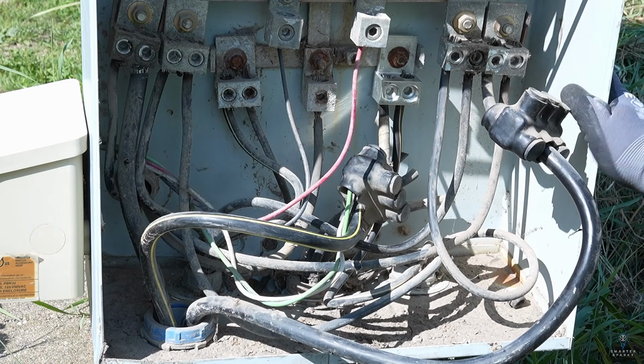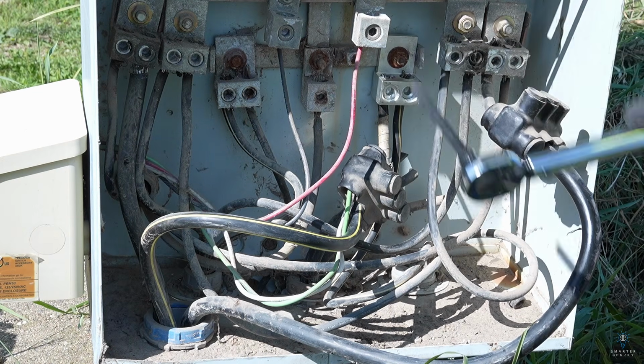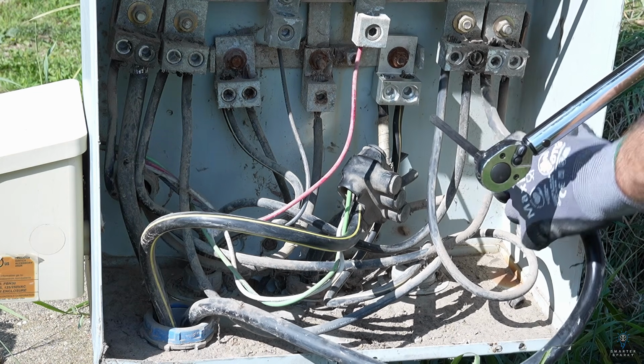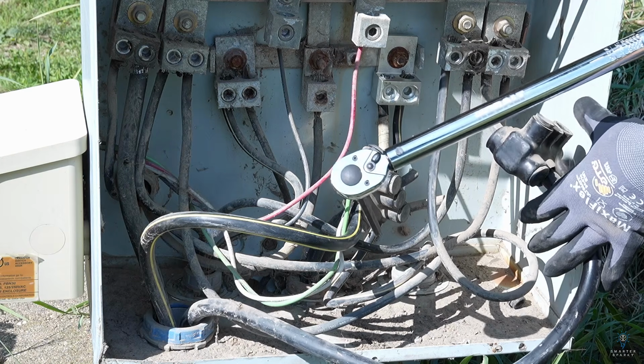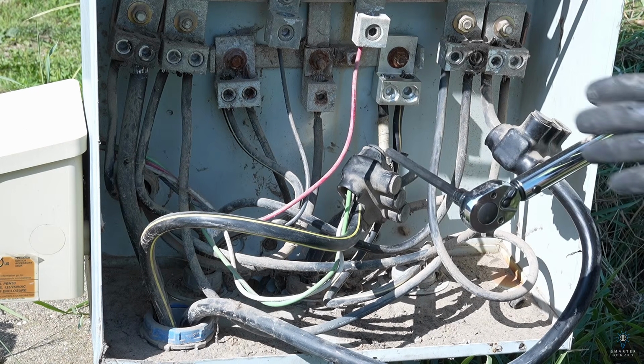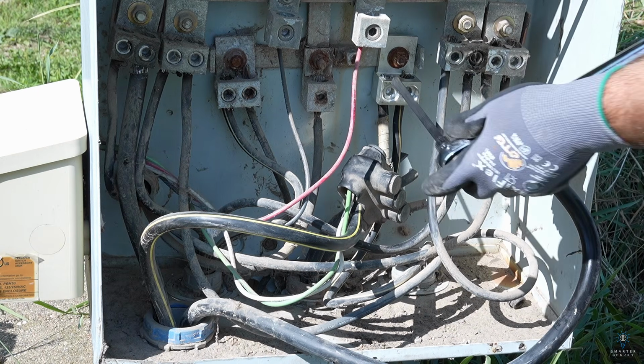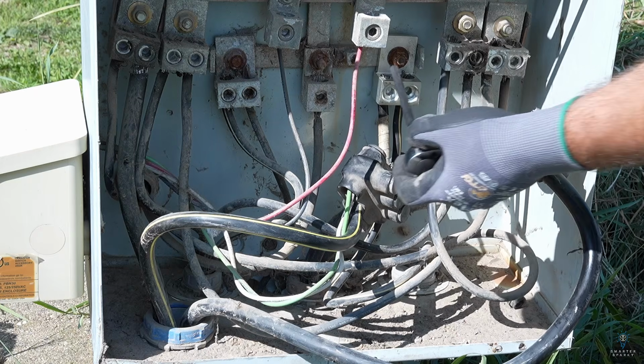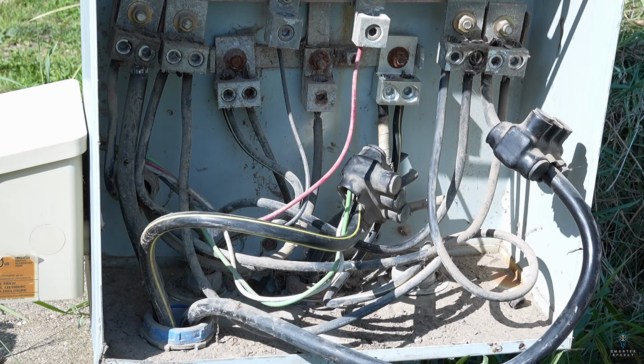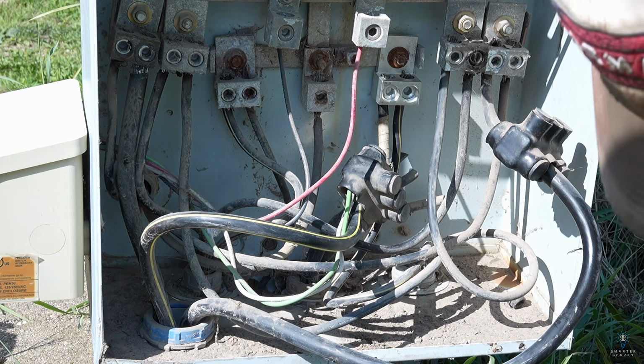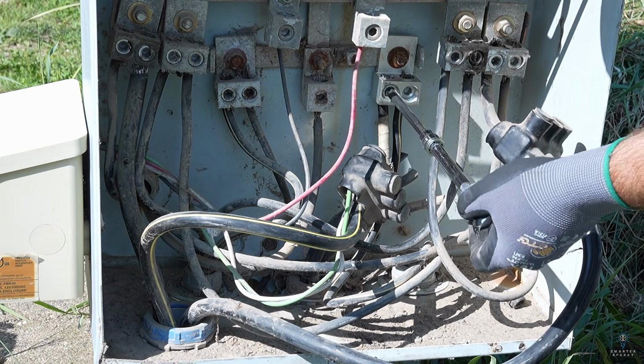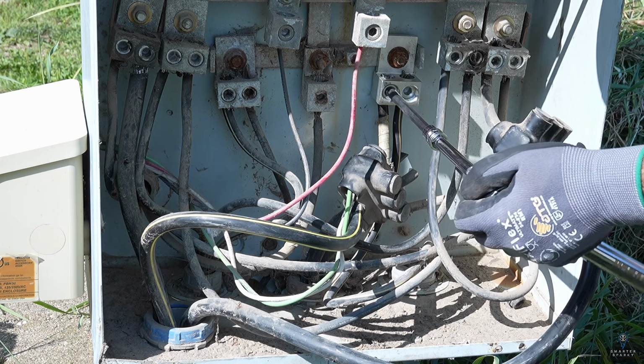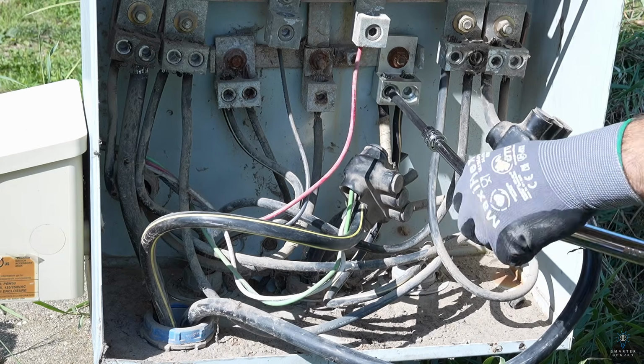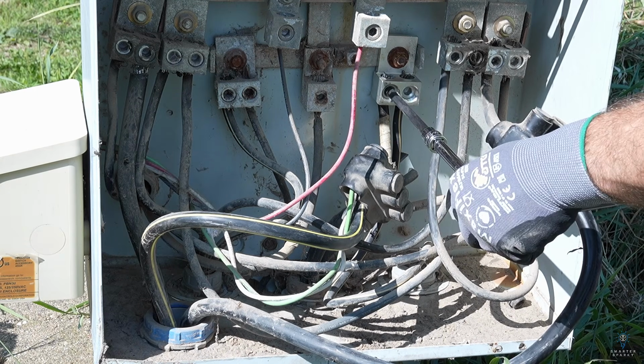I'm gonna grab a different Allen wrench. The proper torque for these lugs is 275 inch-pounds. This is a foot-pound torque wrench, so it's about 23 is approximately what it is. That's kind of on the low end of what my torque wrench can do. I think it's going to be close enough. It looks like I'm going to have to use an extension here. That's going to slightly change the torque. I'm not worried about it. Probably not great to use a swivel either, but it is what it is. There it is.